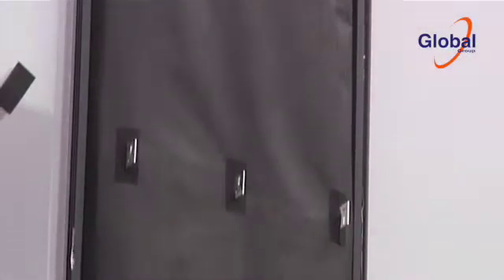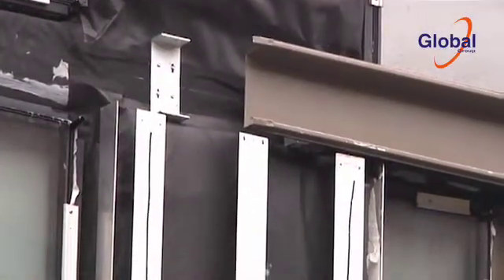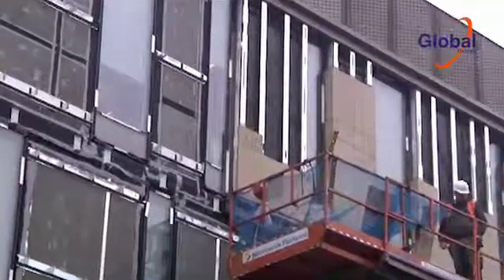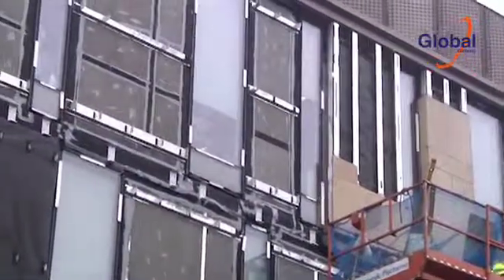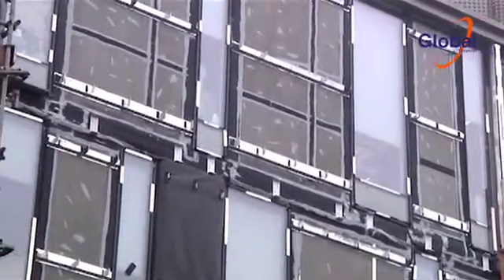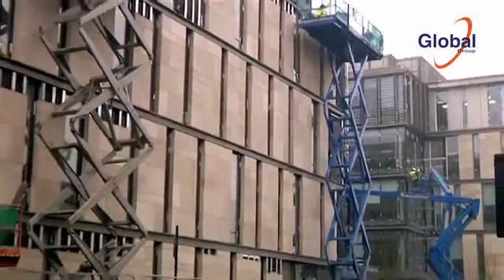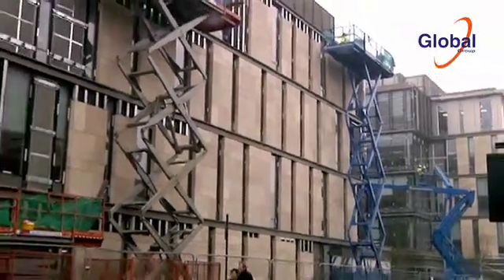A fire risk assessor may be unable to adequately check the cladding or facade construction. Therefore, the installation records provided by the installer should be examined. If there is any doubt about the safety of the installation, a specialist third-party organisation should be engaged to determine the condition of any cavity barriers, and the results of all inspections must be recorded for future assessments.